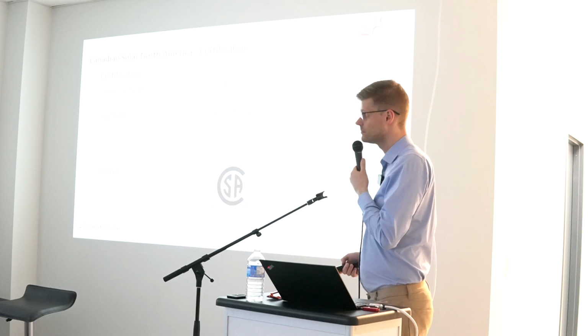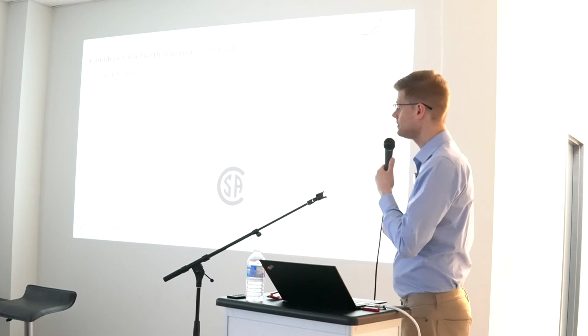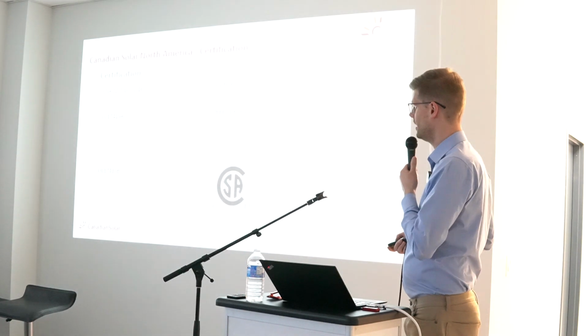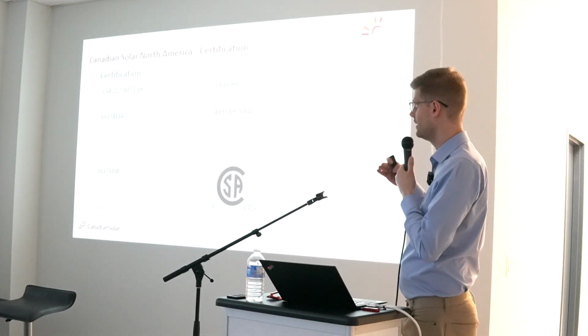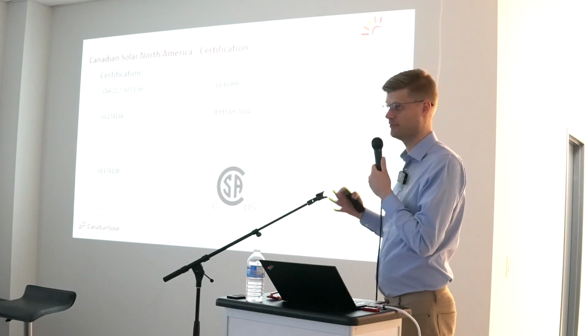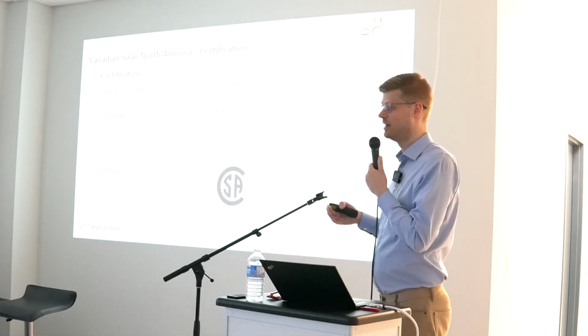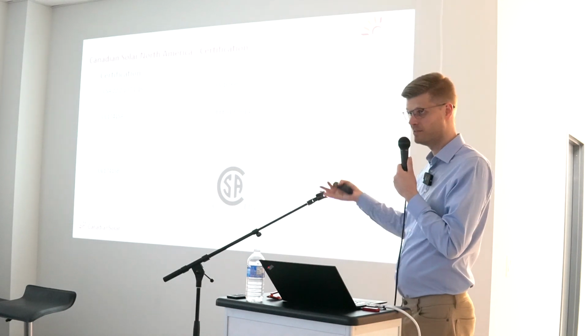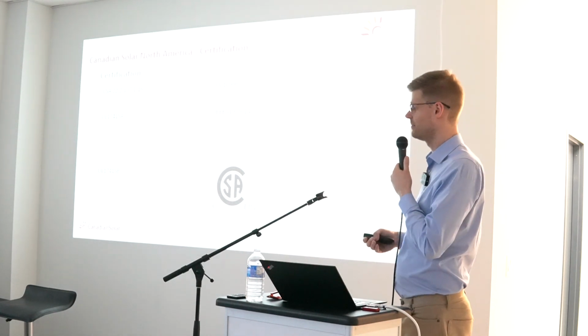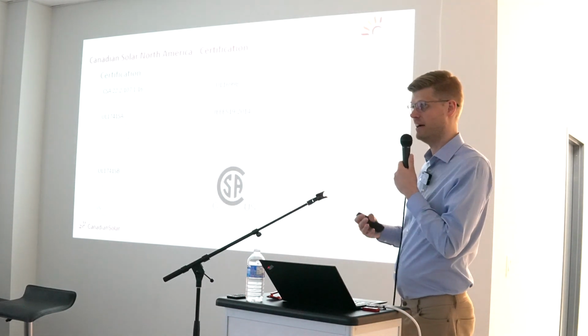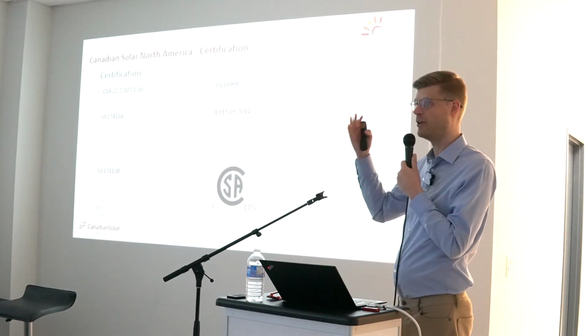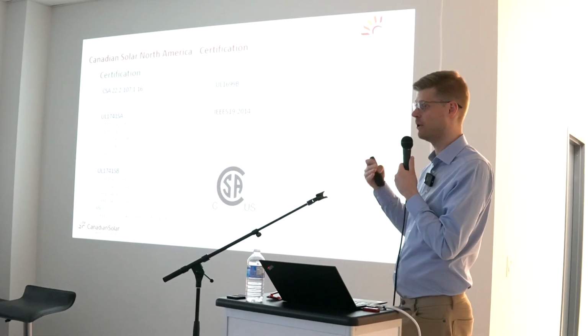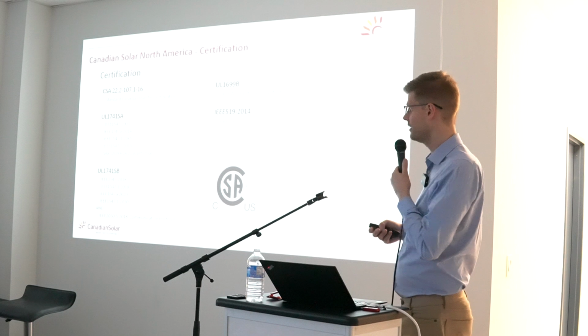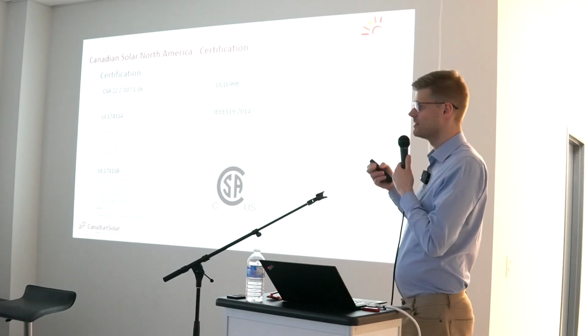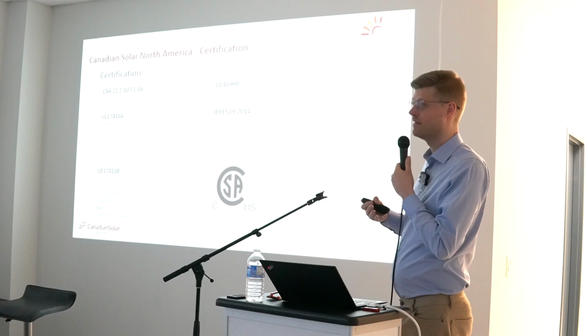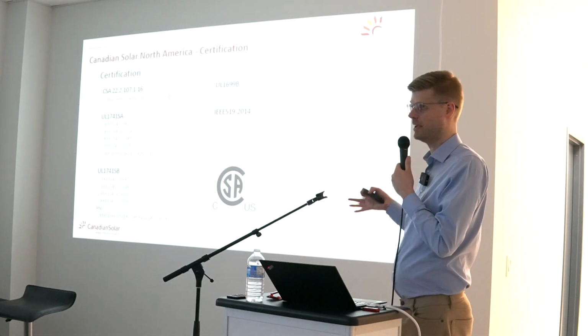Can you talk about why the US companies a lot of times don't have AFCI on their 1500 volt units? Certainly. In the US, for rooftop installations, the voltage limit on the DC side is typically 1000 volt. So commercial and C&I systems are installed with a regular 480 on the AC side and 1000 volt on the DC side. For a 600 volt device on the AC output side, you try to have a higher input voltage to design the most efficient and cost efficient electronic power stage. And since 1500 is not allowed on a rooftop, this product will automatically go into a ground mount application only.